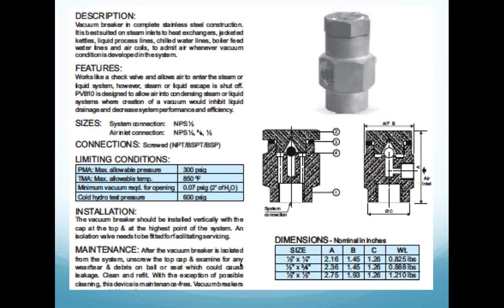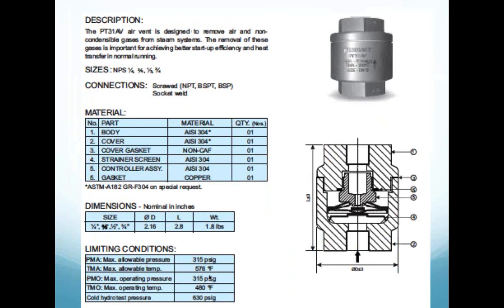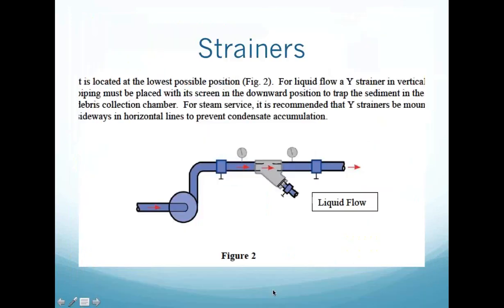I don't want you to use vacuum breakers on those, but on any of the rest of the steam heating equipment that you have, whether it's coils, platens, or heat exchangers, I want you to make sure that you use vacuum breakers and air vents properly. They're simple devices, they're invaluable, and you won't believe the actual processing ability of them.